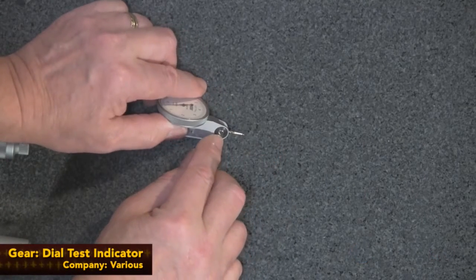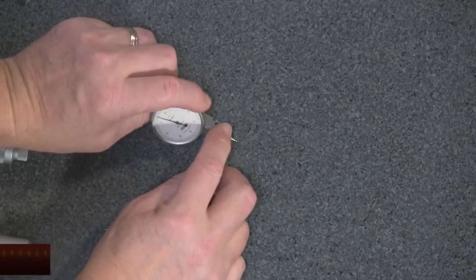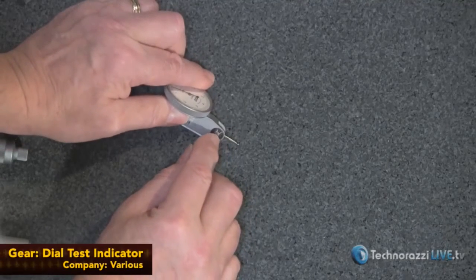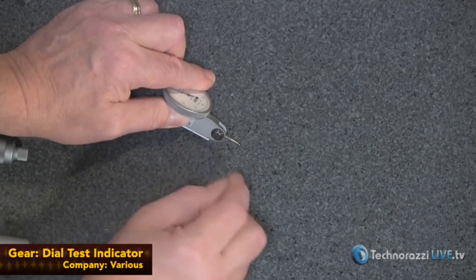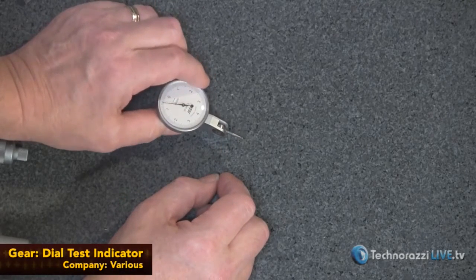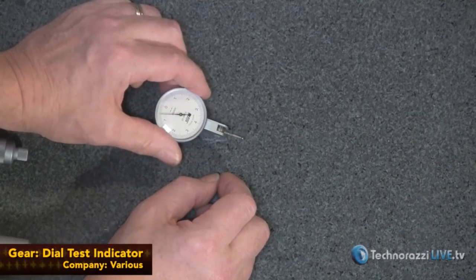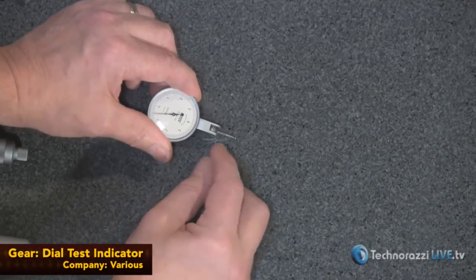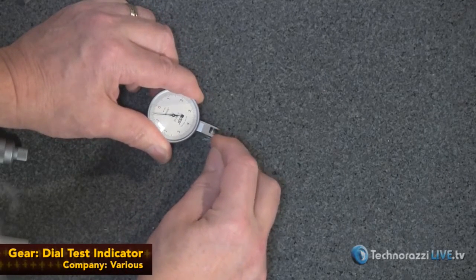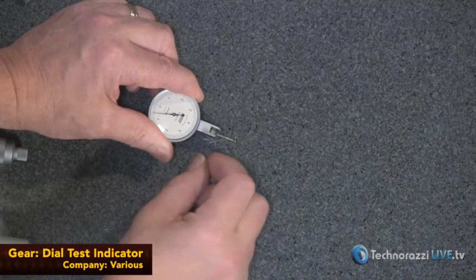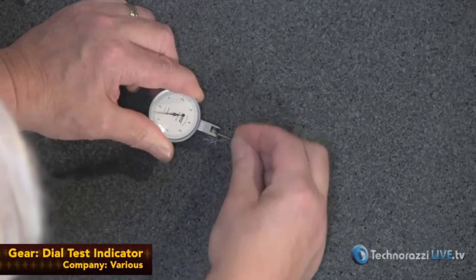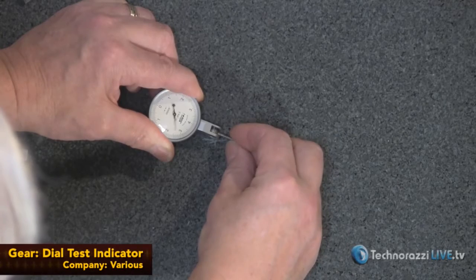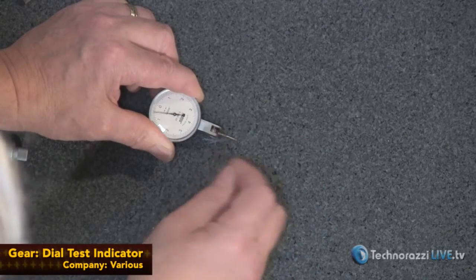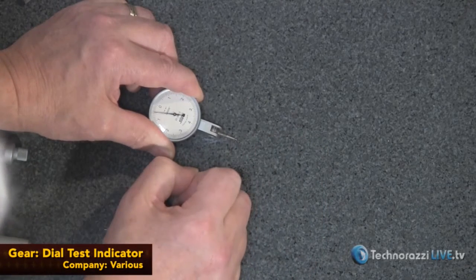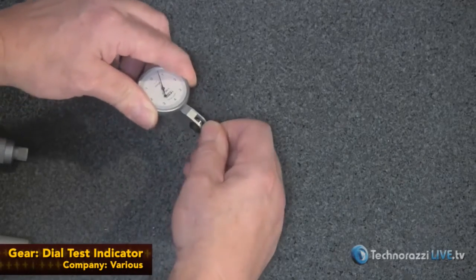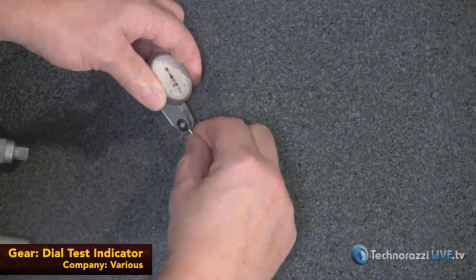We'll look at, usually these have screws. This is a little different type. This is a compact indicator, but most of them will have a little adjustment screw. Look and see, are the screws all burred up? That means someone's been in there adjusting that really might not have known what they were doing, or they wouldn't have left burrs on it. Check for buildup in here. These screws are usually ball bearing screws, so we try to wobble this back and forth and make sure it does not move back and forth. If it does, those ball bearing screws are either not adjusted right or they're damaged. So that shouldn't have any play left to right.